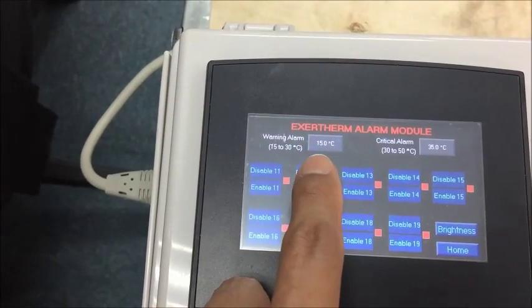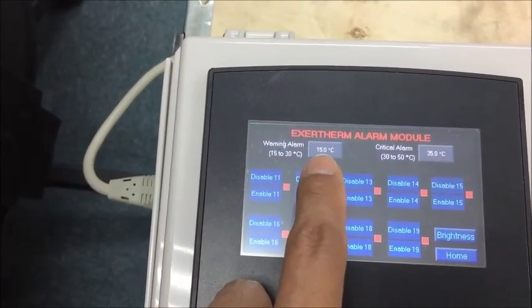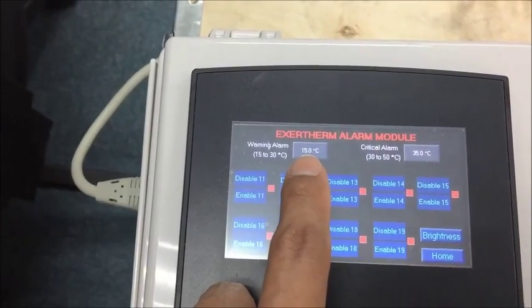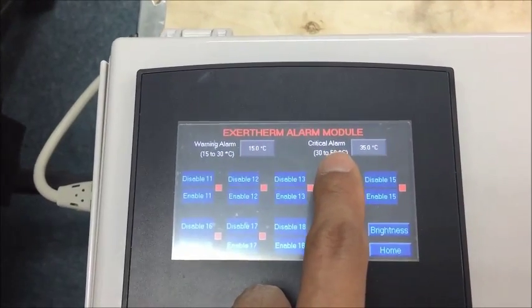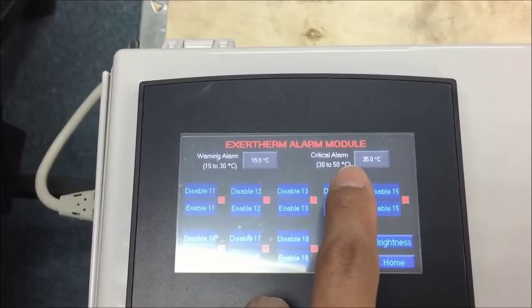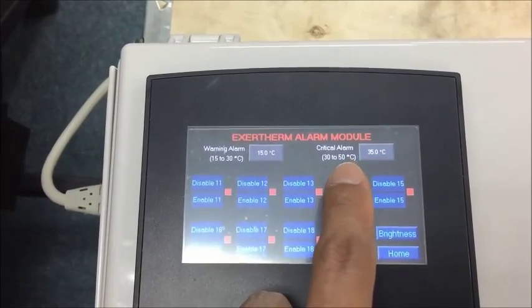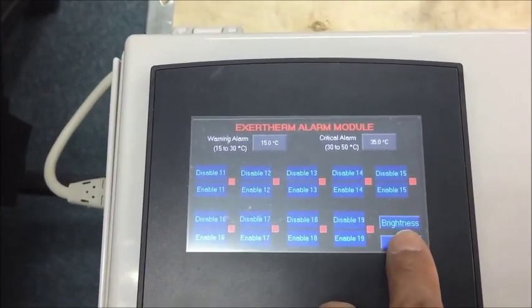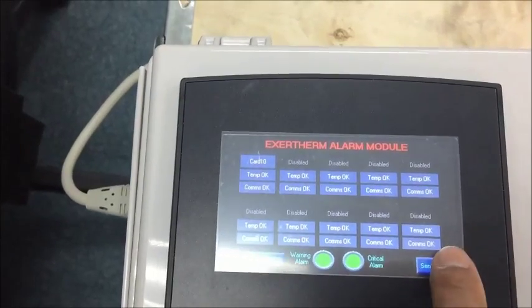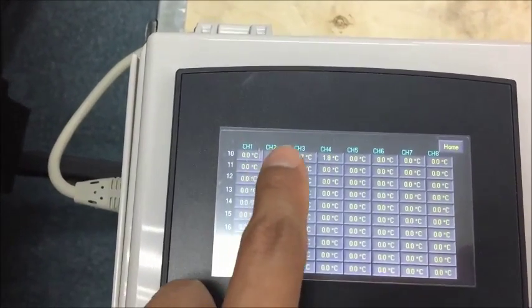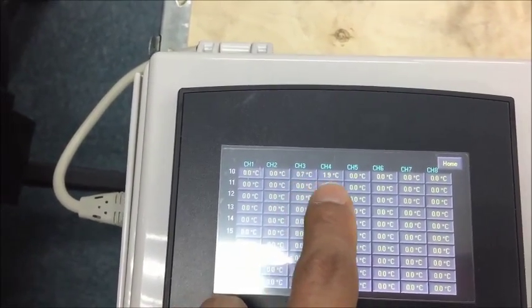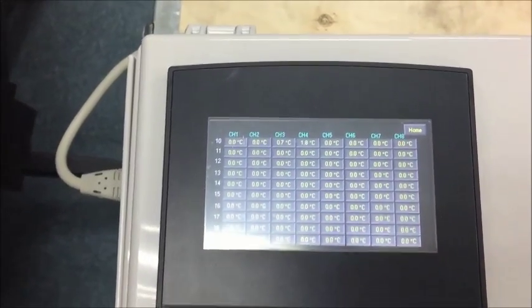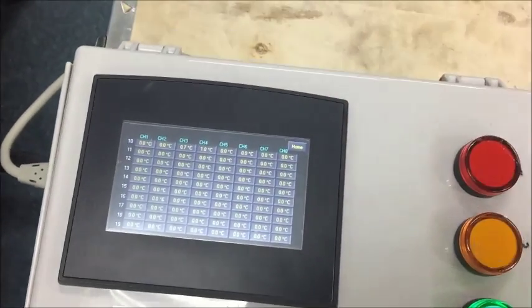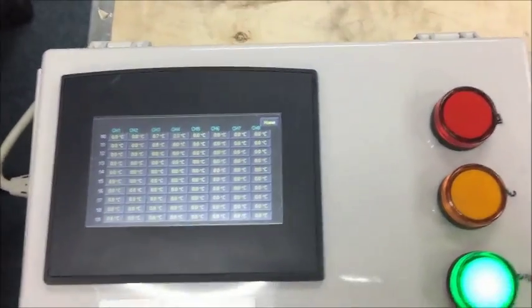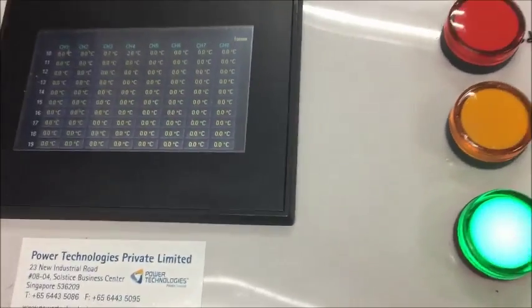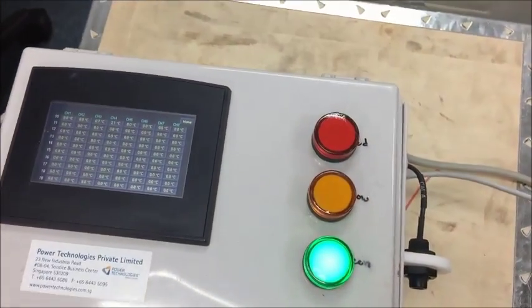So we set at 15 delta T difference degrees Celsius for warning alarm, and 35 degrees Celsius delta T for critical alarm. And we can see the sensor view, and we only connected 2.